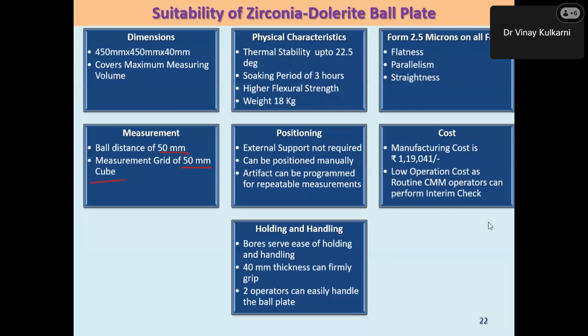Now just imagine that if you want to make it by using laser interferometer or any other dimensional checks, the cost of the calibration of that CMM itself is going to be high. Now in that kit, the cost is only 1,19,041 rupees, in which we have programmed also. The program is also ready. We have to just fetch it to the machine. It calculates the errors.